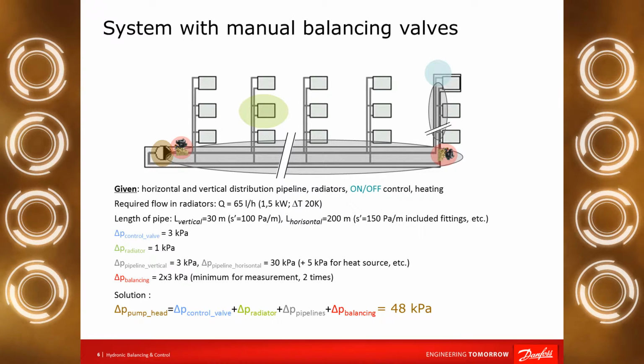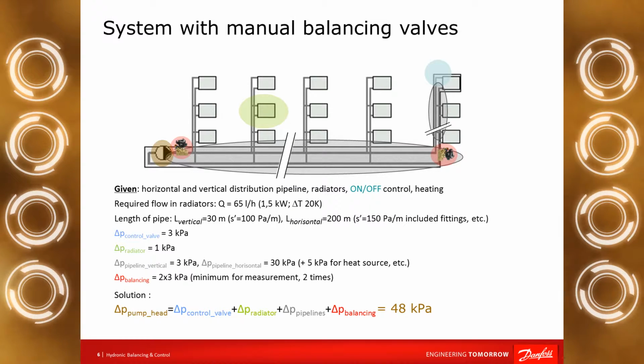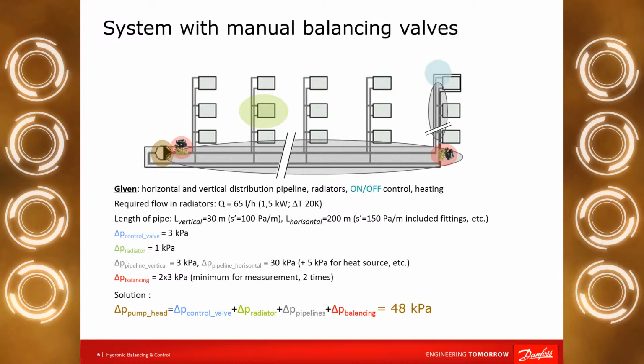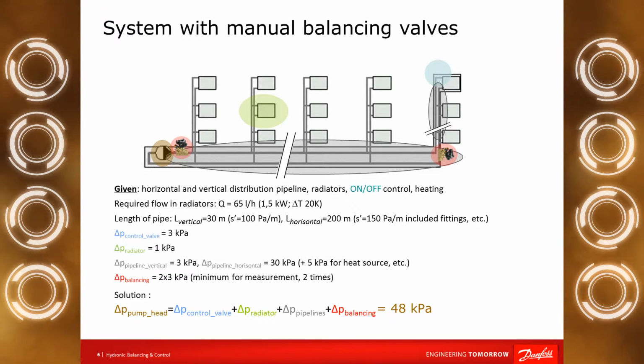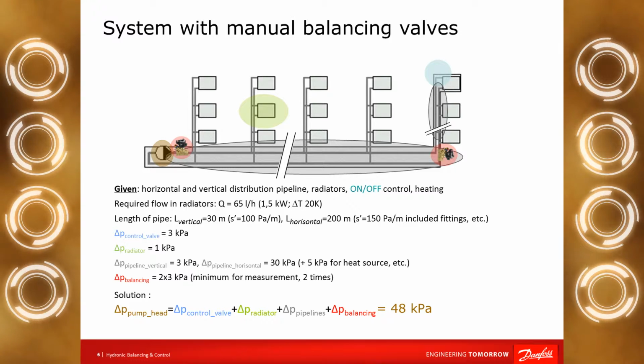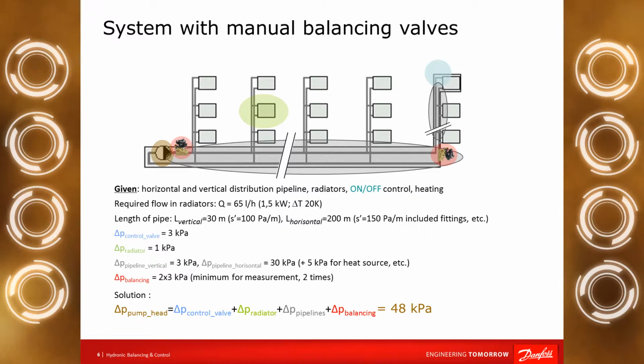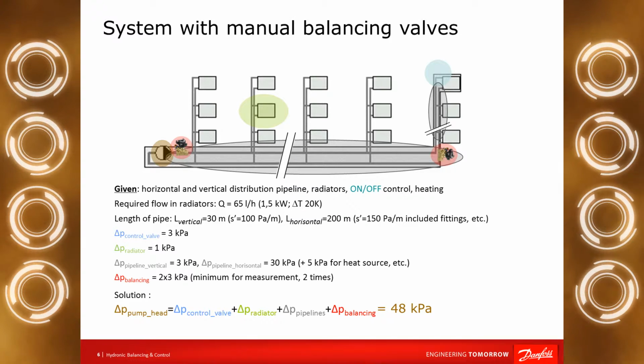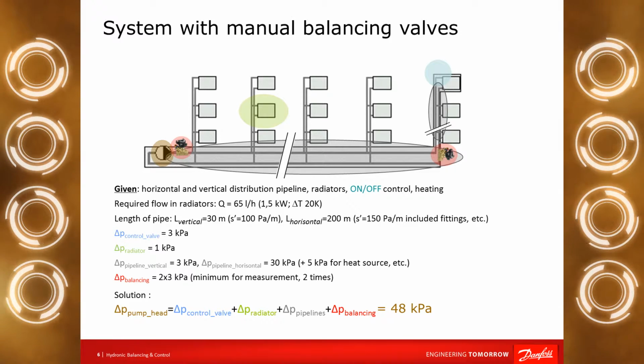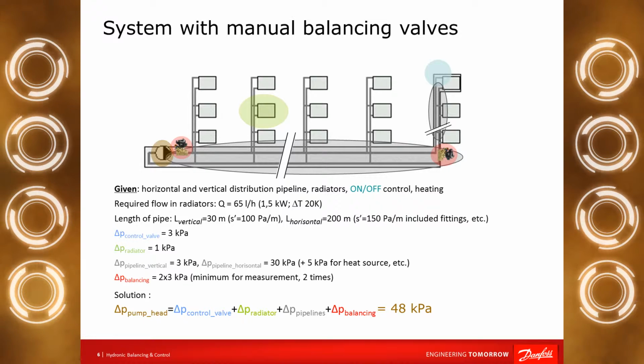The details of the system, as I mentioned, have not changed in this slide. I only have to add a few more details: the delta P demand of the control valve on the radiator is 3 kilopascal, the pressure drop on the radiator is 1 kilopascal, and I use manual balancing valves at the bottom of the risers, which need a minimum of 3 kilopascal for proper measurement and to set the right flow rate on the different risers. If we add the total pressure drops of the system together, we get the pump head, how many kilopascal we need for pumping. It's quite simple and easy.